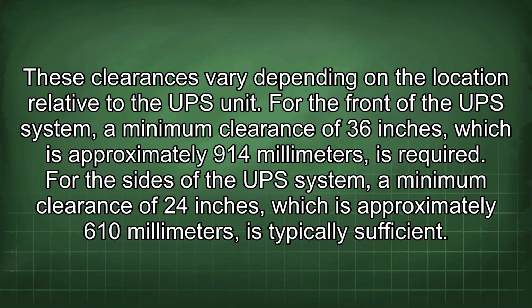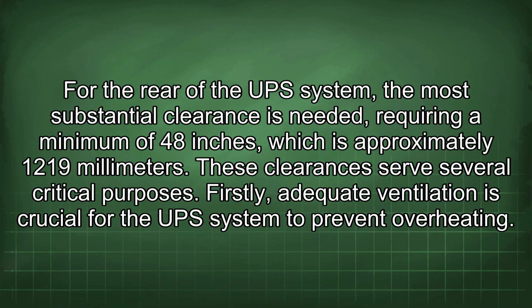For the front of the UPS system, a minimum clearance of 36 inches, which is approximately 914 millimeters, is required. For the sides of the UPS system, a minimum clearance of 24 inches, which is approximately 610 millimeters, is typically sufficient. For the rear of the UPS system, the most substantial clearance is needed, requiring a minimum of 48 inches, which is approximately 1219 millimeters.